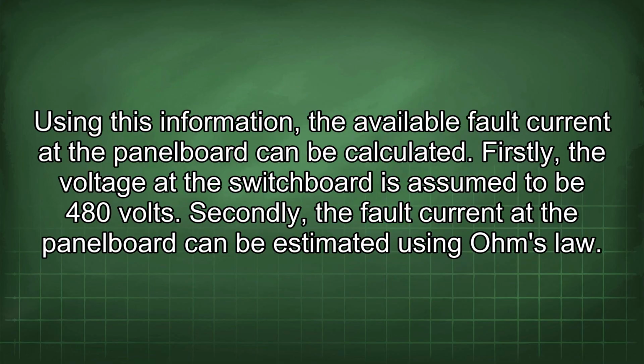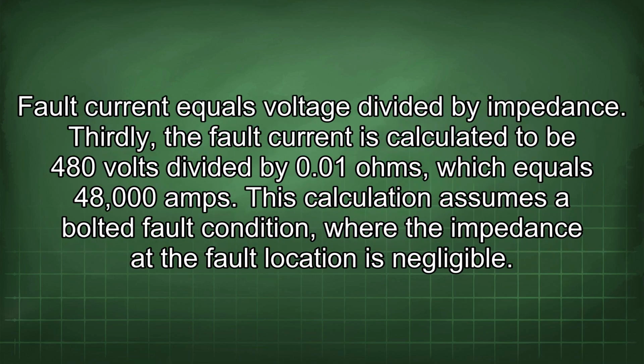Using this information, the available fault current at the panel board can be calculated. Firstly, the voltage at the switchboard is assumed to be 480 volts. Secondly, the fault current at the panel board can be estimated using Ohm's law. Fault current equals voltage divided by impedance. Thirdly, the fault current is calculated to be 480 volts divided by 0.01 ohms, which equals 48,000 amps.